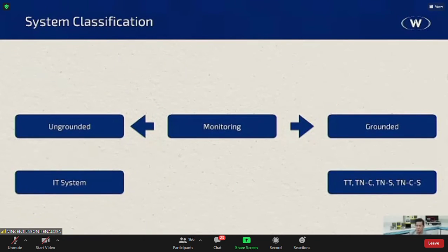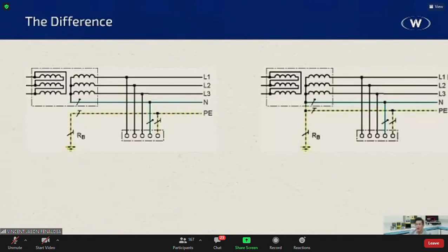So, system classification. We'll be talking about a couple of things, basically just ungrounded and grounded systems, based on monitoring. You will see down there, it's called the IT system. That's not information technology, that's actually isolated Terra. Terra is ground, isolated, that's how it's connected. So it's isolated Terra. It's ungrounded, some call it floating or isolated. The grounded systems come in different versions. You have the Terra, coupled Terra neutral, and so on and so forth. Now, what is the difference? Chances are all of you know this already. Now, which of these two diagrams is ungrounded?